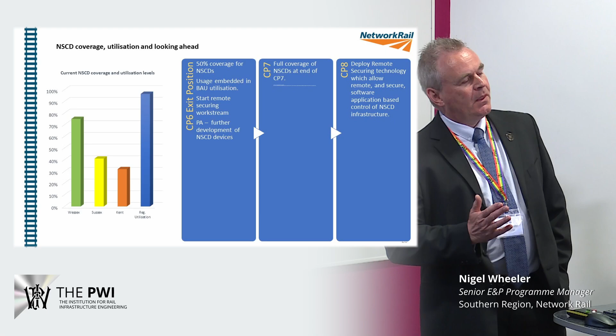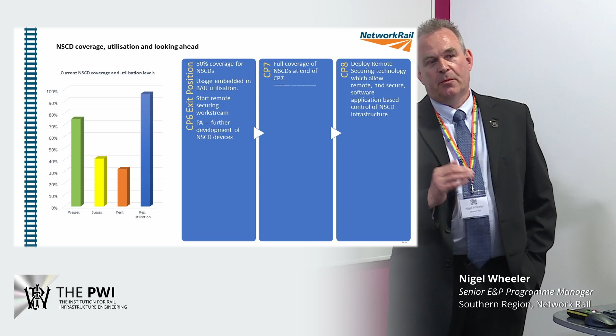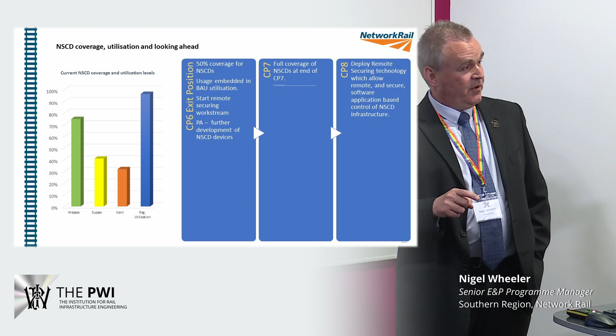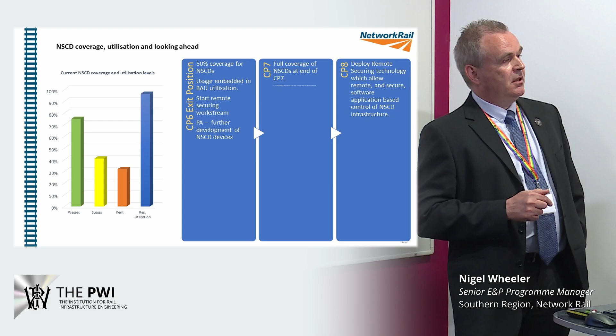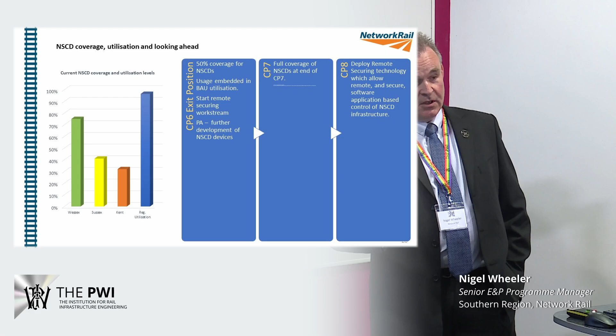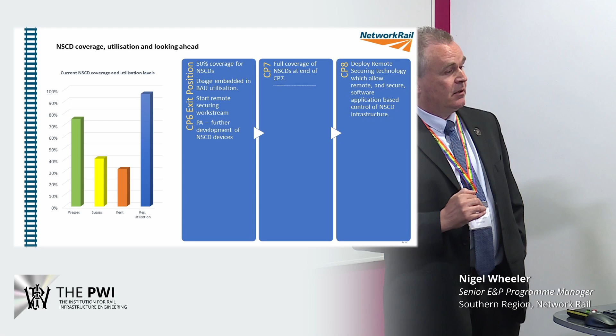By the end of CP7, the intention is, provided we get the funding, that all fixed equipment at substation TP huts will be fitted with NSCDs, and the most commonly used hook switches or trap disconnectors will be replaced by CTSs. That's tinged with the condition that we don't yet know what we're getting in the CP7 settlement, but we're making a very strong case for this on the basis of safety and the other benefits we get from doing this work.